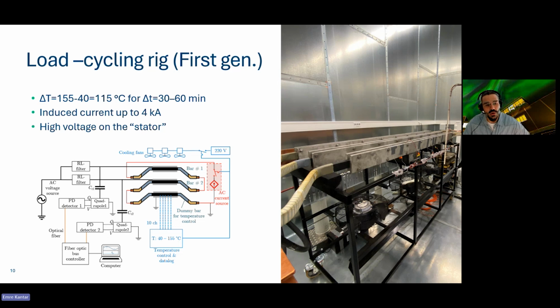I'm not going to go into the details a lot, but what we did here is that we used 2 bars and circulated a heating current in these bars, and we used a third dummy bar in which we installed some thermocouples inside the copper and outside of the insulation to record the temperature. Whenever it hit the maximum set point, it stopped the heating current and started blowing the fans, and it continued like that for the entire start-stop or load cycling period.